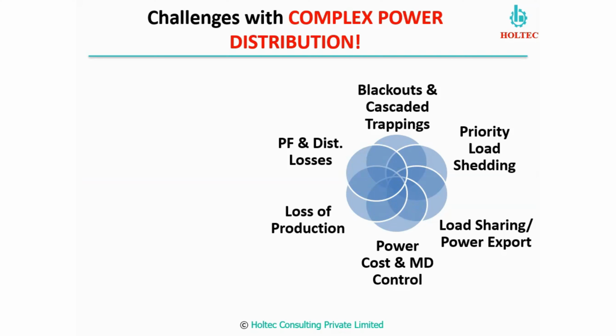There are fluctuations in the loads. Sometimes these fluctuations are in the range of 2-3 megawatts also. Suppose we want to keep 1 megawatt on the grid, and we have a reverse power tripping also. Because of this fluctuation, your load on the grid will become zero, and your reverse power will operate. So what are people doing? We bypass the reverse power, and these slight variations in the load actually go reverse to the grid. So this is happening.